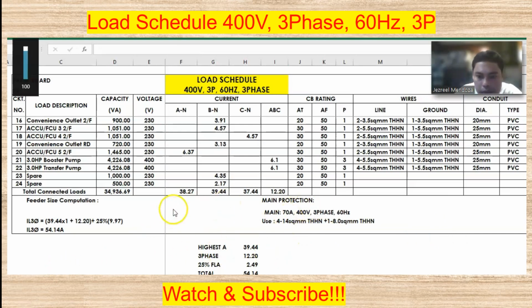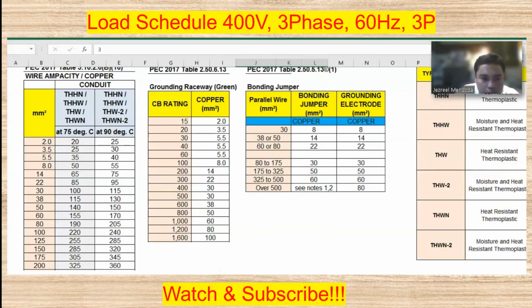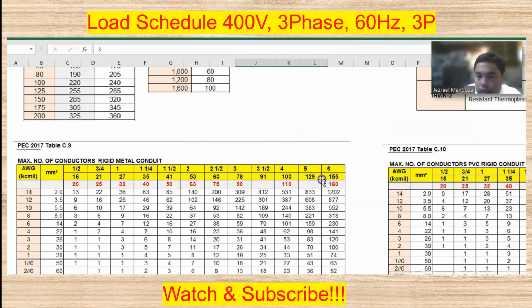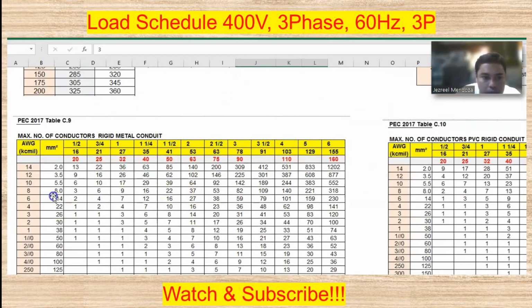if we look to the PEC table, for the main feeder wire, we can use the steel conduit. So we have in 14, for 50% fill, we can use 40 mm. Our wire is 14 square mm.